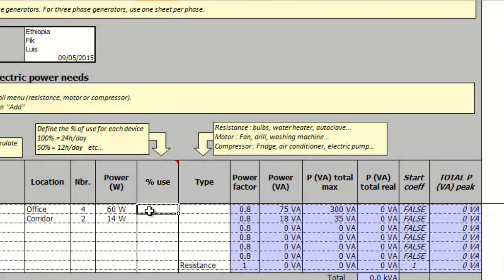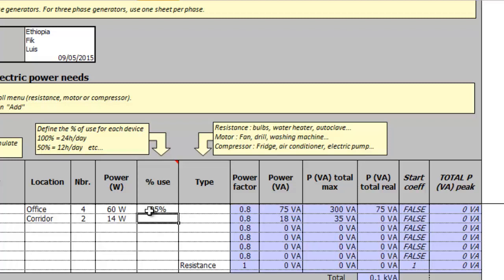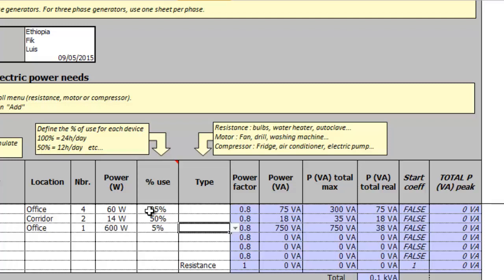The next column regarding the use represents how many hours per day the device is consuming electricity expressed as a percentage of a day. This means that 10% is 2.5 hours, 25% is 6 hours and so on. There are some appliances, like printers for instance, that even if they are plugged and turned on they only consume power rated on their plate when printing. We should take this into account when filling this column so the total consumption is as accurate as possible.